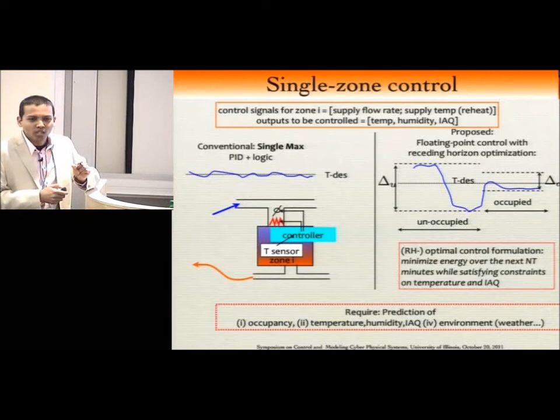The reason is that when suddenly the room becomes occupied, if the temperature is far off from a comfortable range, it will take a long time for the temperature to be brought back. This is also why the approaches people use in smart lighting, for example, are not really applicable. The physical phenomena governing this have a slow time scale—it takes about 15 to 20 minutes after you turn on the vents for the temperature to come up.